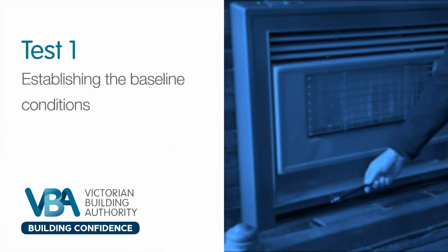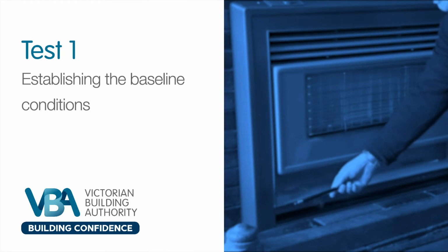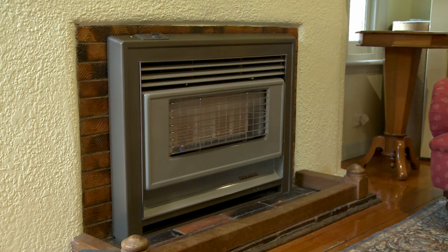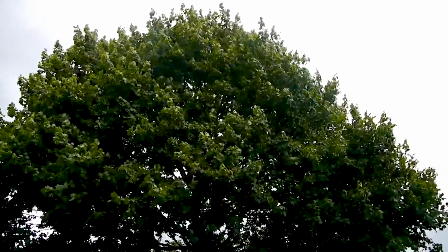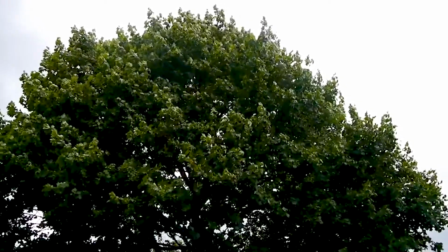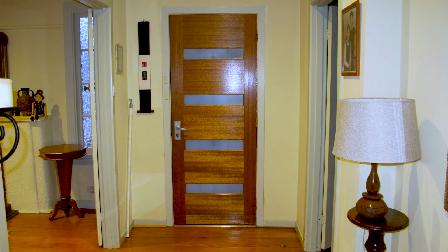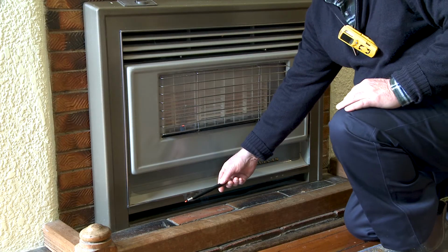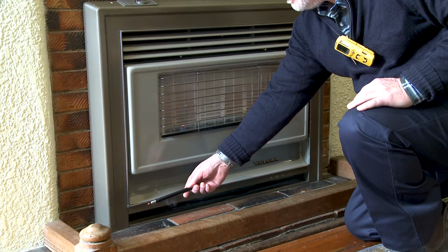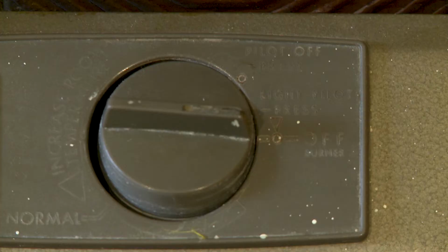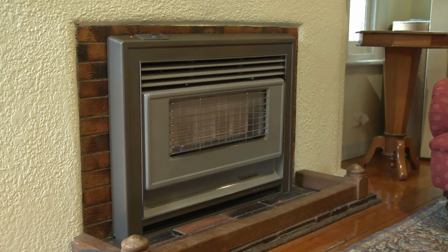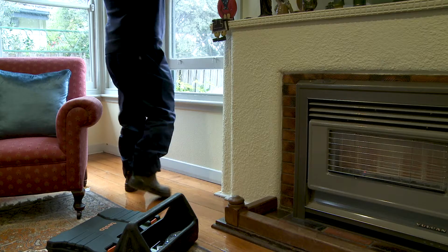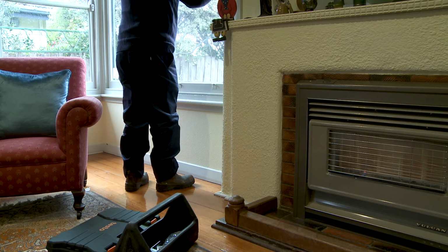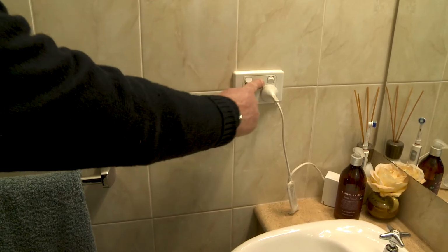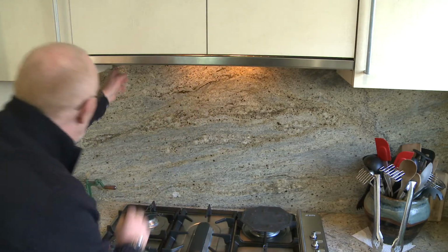Test 1. Establishing the baseline conditions. The purpose of the baseline test is to establish if weather conditions such as wind gusts or the temperature differential between outside and inside will impact on the smoke test. Any effect should be considered when conducting the smoke test. Ensure that the gas heater is off, is at room temperature, and that the flue is cold. Close all external doors and windows. Ensure that all extraction fans and range hoods are switched off.